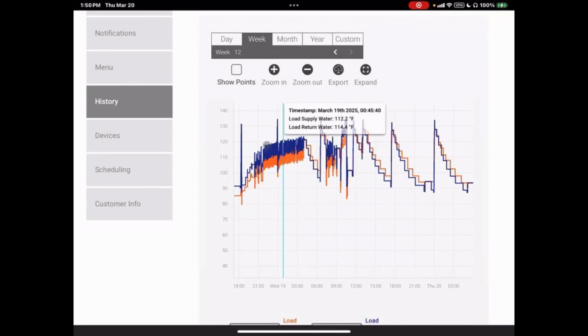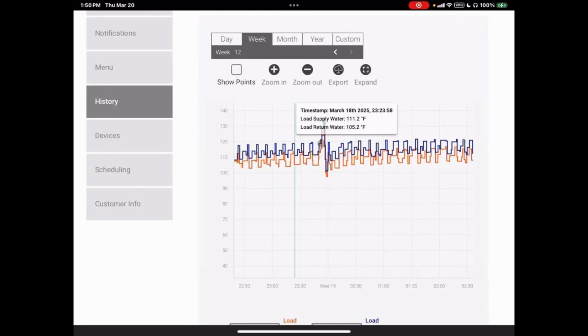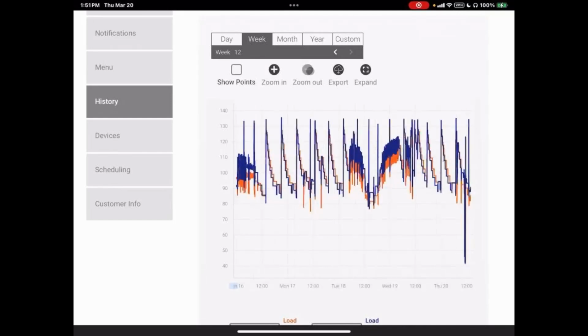So let me zoom in on that section a little bit more. So from the time that we got the hot water call, say right there, call it 2350. The hot water call was over by 58, 59, call it. So 8 or 9 minutes that the unit ran in domestic hot water. That's not enough time for you to see any sort of issues or problems with the space cooling down, if that makes sense. You got anything that you want to add about that, John?